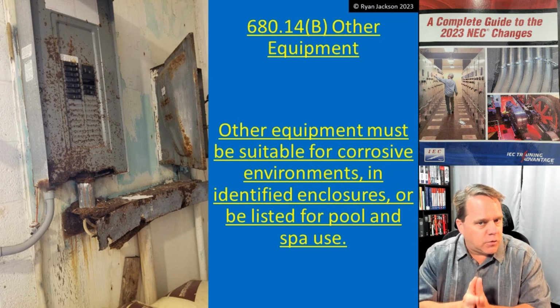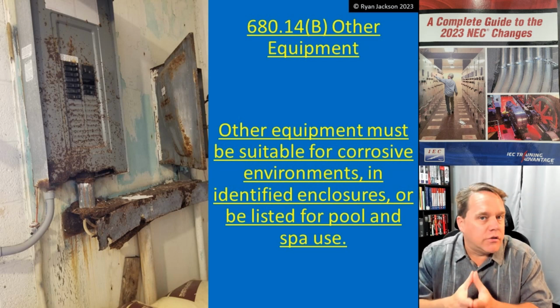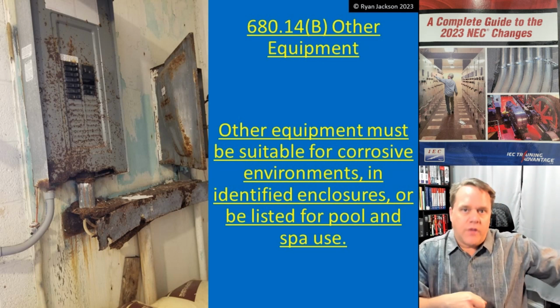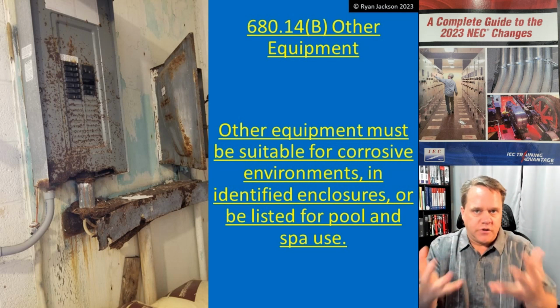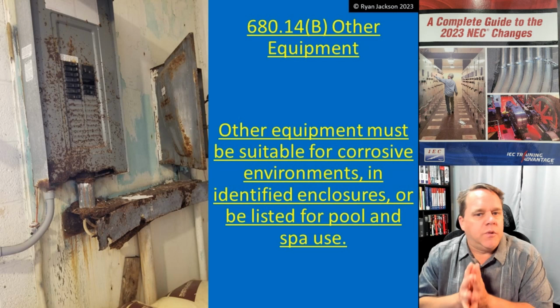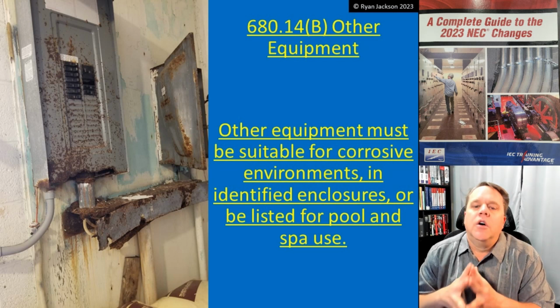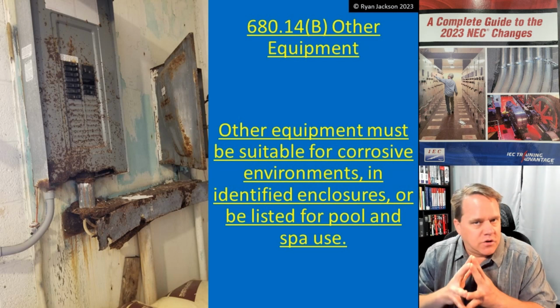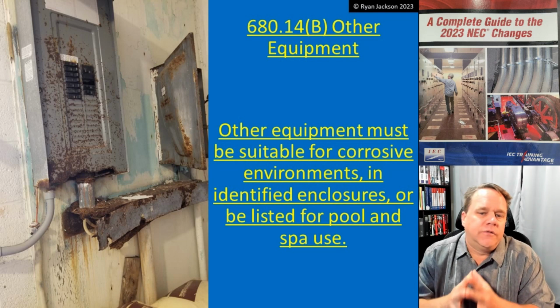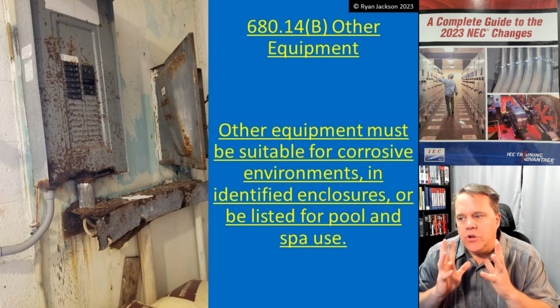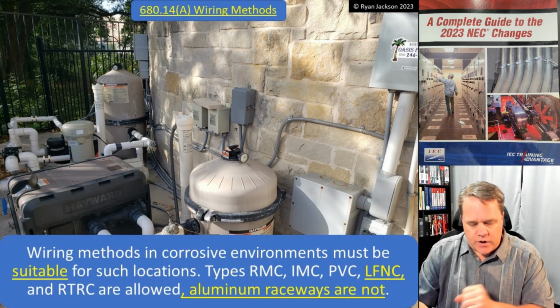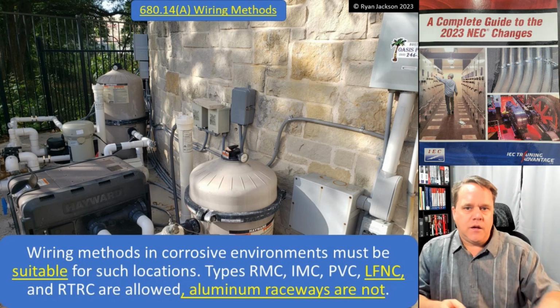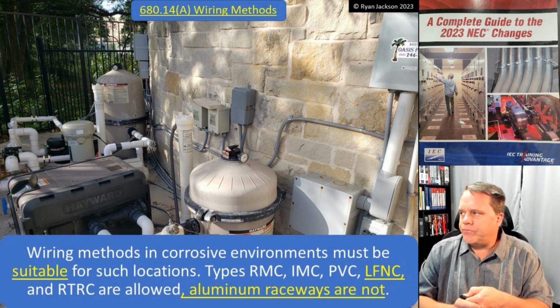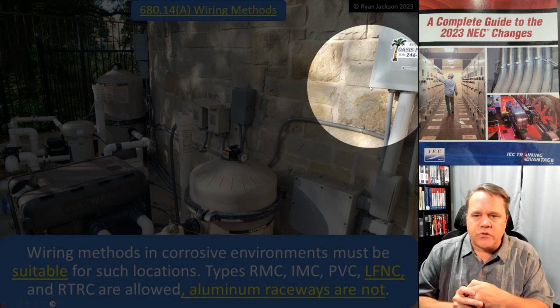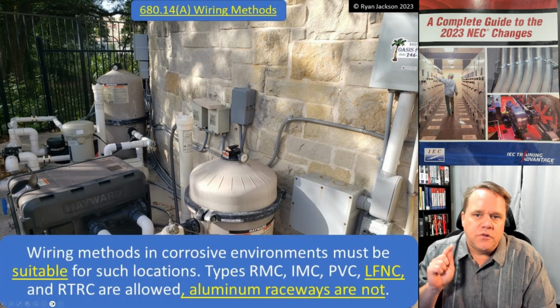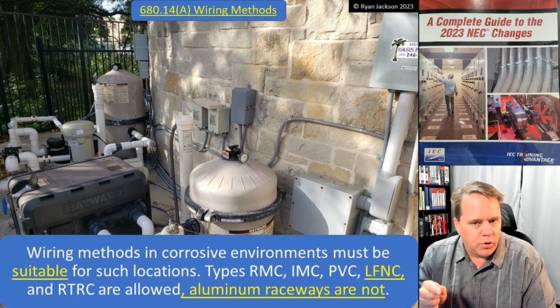So 680.14(B) says other equipment, other as in not the wiring methods, so panelboards and enclosures. Other equipment must be suitable for corrosive environments, or be in identified enclosures, or be listed for pool and spa use. If I go back to this photograph, in the top right-hand corner of this picture, that is almost certainly a listed swimming pool and spa panelboard.